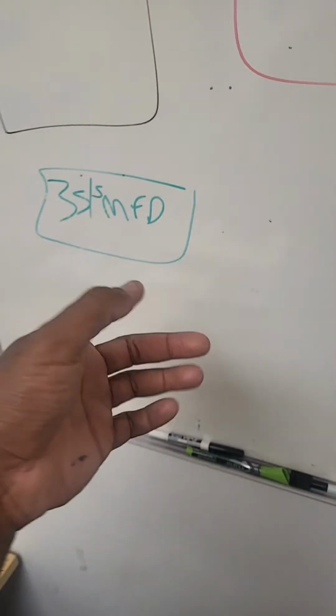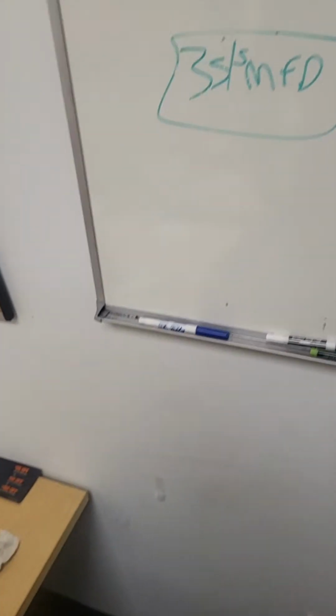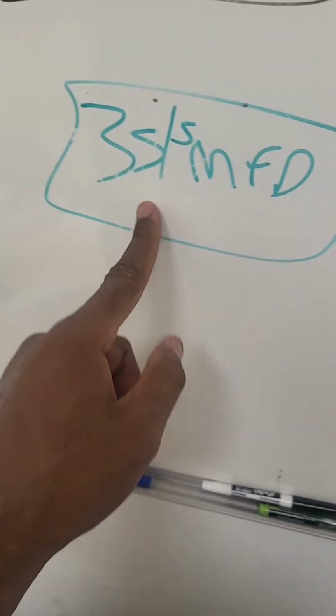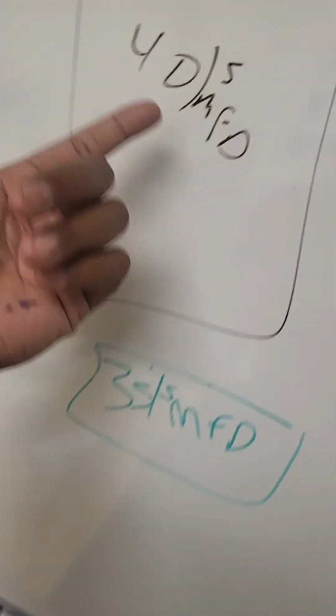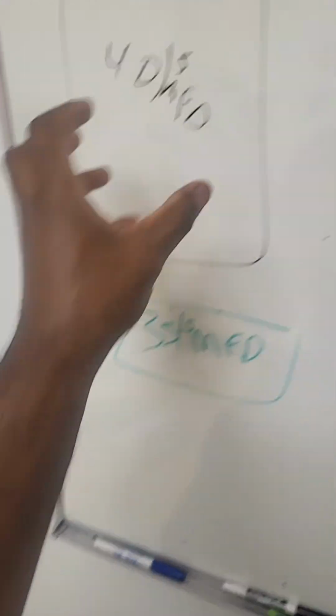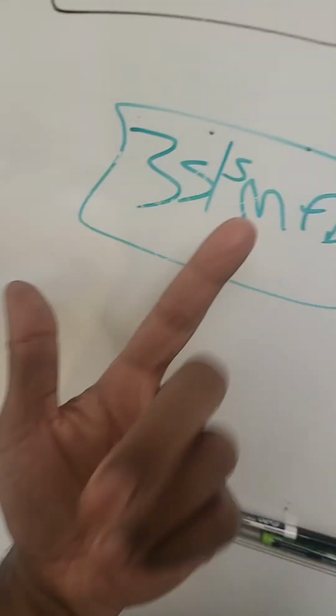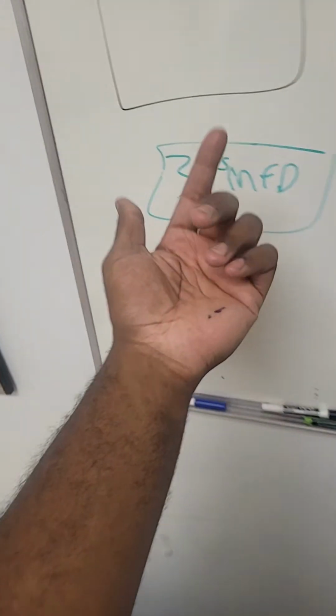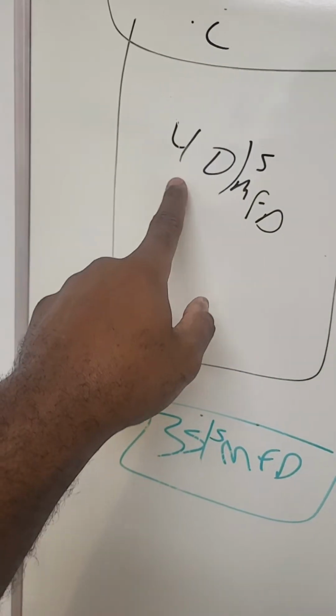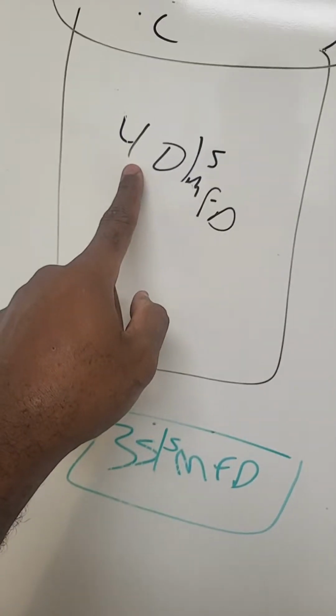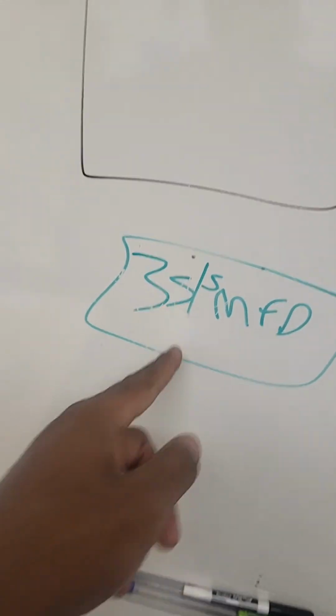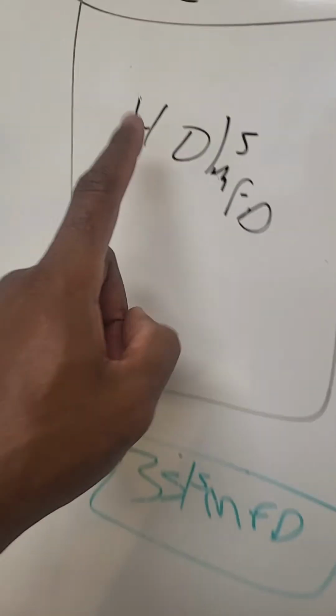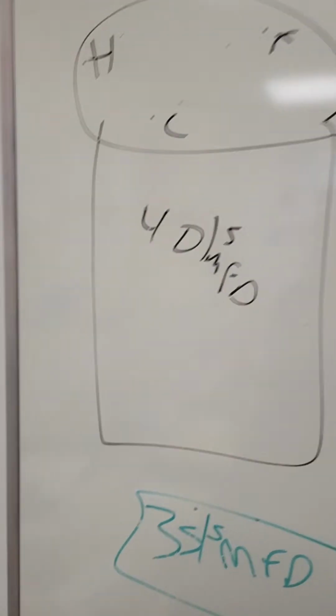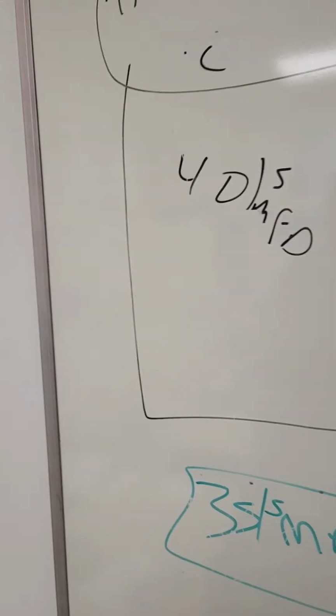Reason being, guys - and I don't feel like I have to draw this on the board - if you put a bigger cap in than what it's rated for, I don't care if it's 40-5 or 45-5, it could alter the starting torque, and before you know it, this bigger cap could alter the starting torque and eventually cause issues with either your compressor or your fan motor.